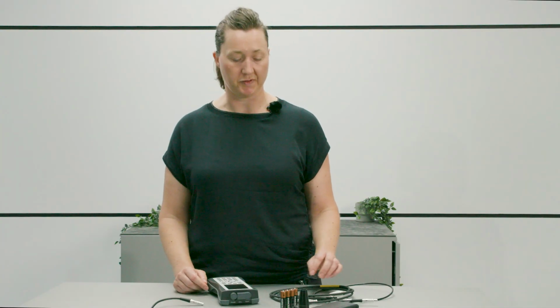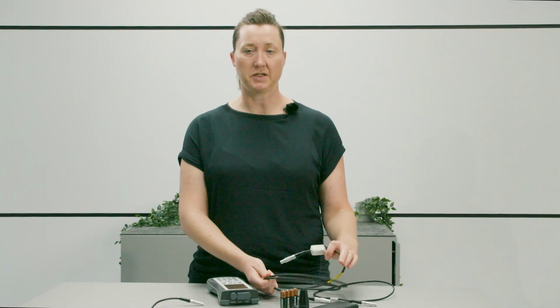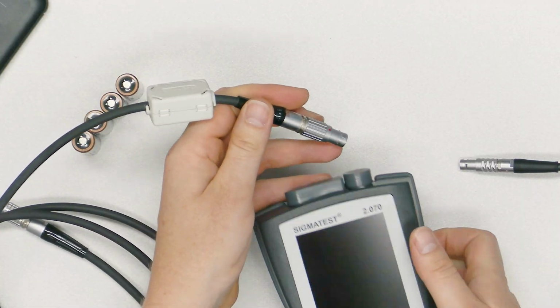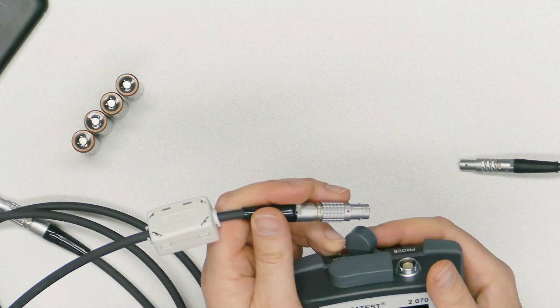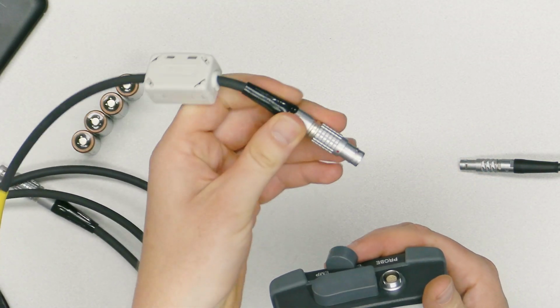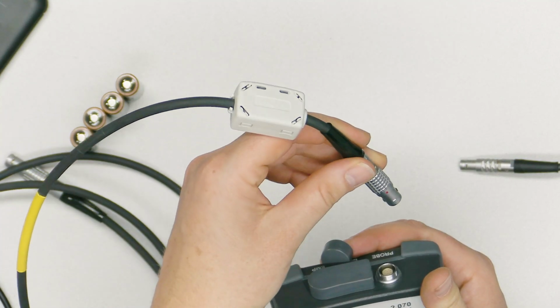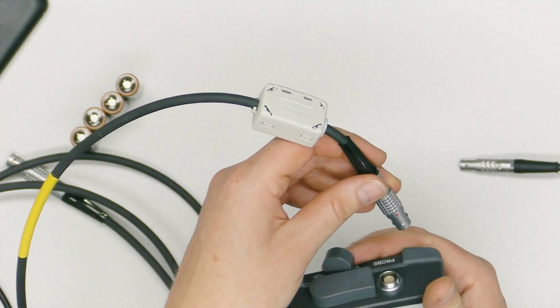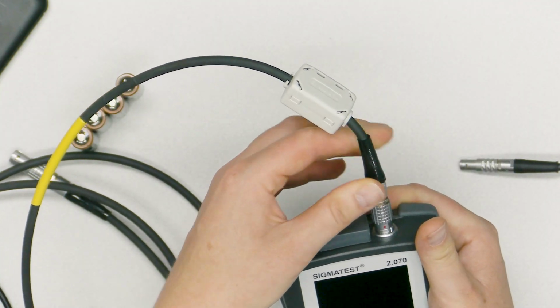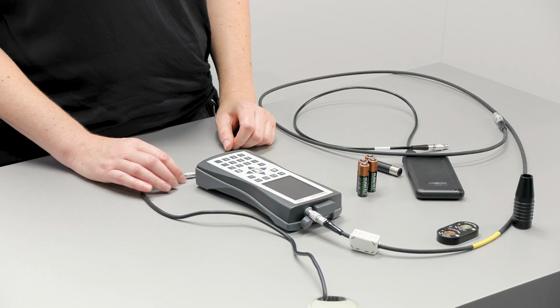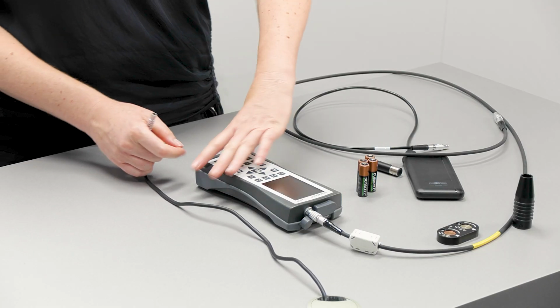Now I show you how to connect the components to the SIGMATEST. Regardless of the mode in which the SIGMATEST is used, the probe cable is connected first. Plug in the end of the probe cable with the ferrite beads, which is a little white box enclosing the probe cable, into the designated socket on the top side of the measuring device. The red dot on the connector must face upwards for the connector groove to engage in the socket. Connect the plug-in power supply or the external rechargeable battery pack.